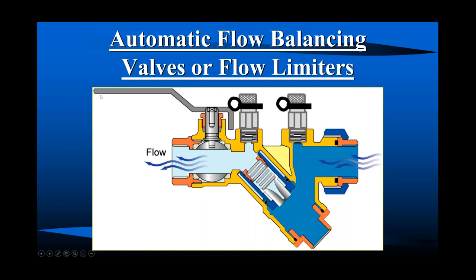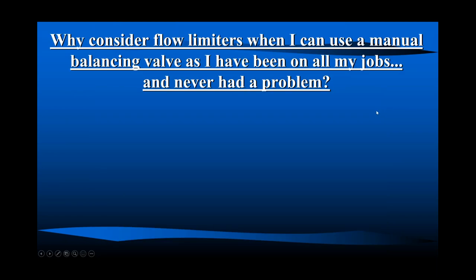This handle right here is not red. It is a true isolation valve. In this case, it's a ball valve. This is not used for adjusting flow. This device right here, again, is the only thing that makes or limits flow in this device. So again, New York City is a very large market for manual balance valves.